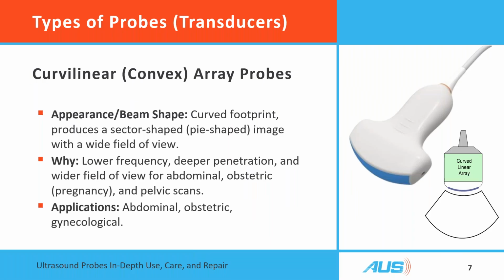So keep that in mind when we talk low frequency. You're talking 2 to 5, 1 to 5 megahertz in that range. Philips, as an example, has one that goes from 2 megahertz to 9 megahertz. But they stay traditionally in the lower frequency for more penetration, which does, in general, reduce the image quality.